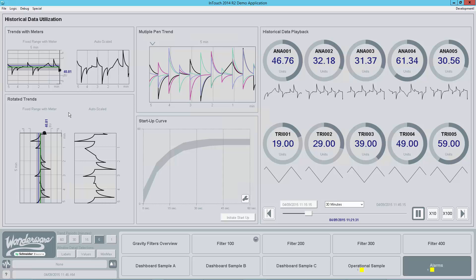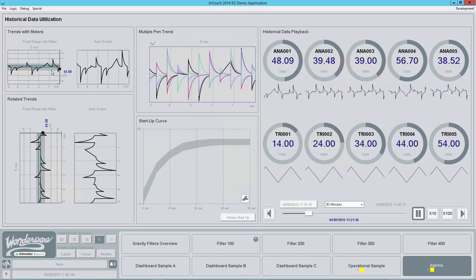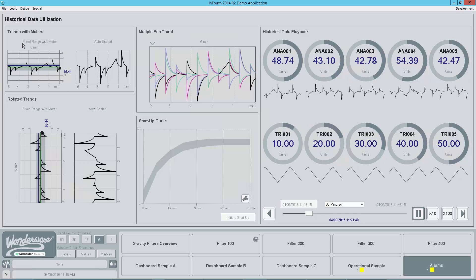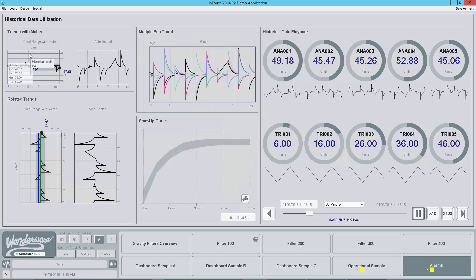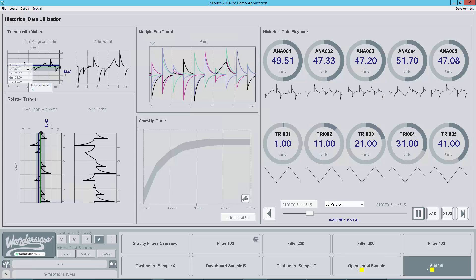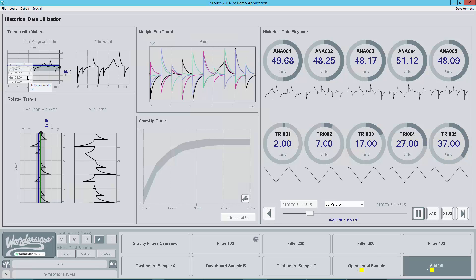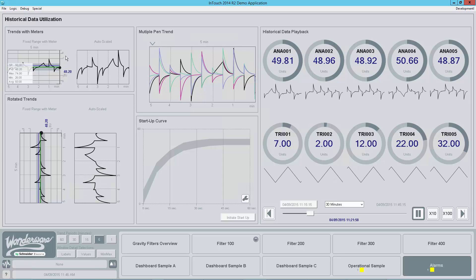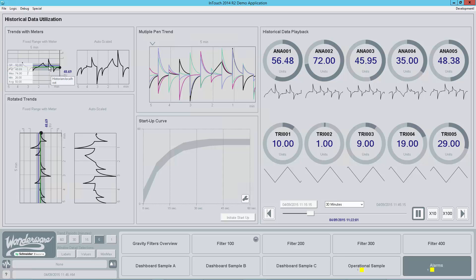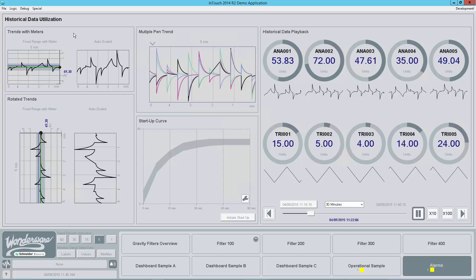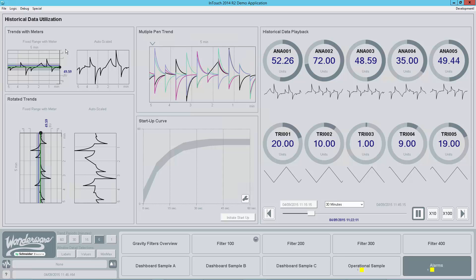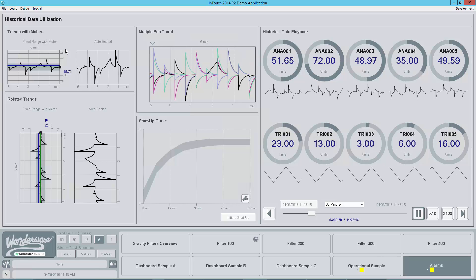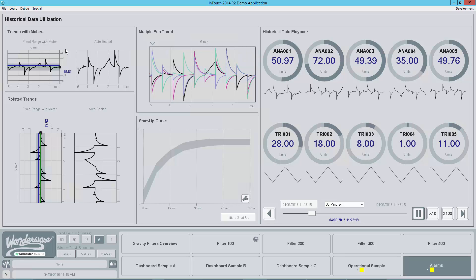You'll see the first one on the left on the top here, these trends with meters, the fixed range with meter is showing that there is a meter on the right-hand side of this. It's using the trend pen that's combined in with some of these lines to be able to provide you contextual information. You'll also see that as I hover over top of this, I'm getting some tool tip information about set points, process variables, the maximum over the period, the minimum over the period, and the average. I can also see here the current value. I can see alarm limits. I can see operating ranges, set points. This allows you to get a very good context of how that particular variable is performing within the system. Again, this particular trend is not targeted at data analysis, but really at supporting contextual information for real-time process control.